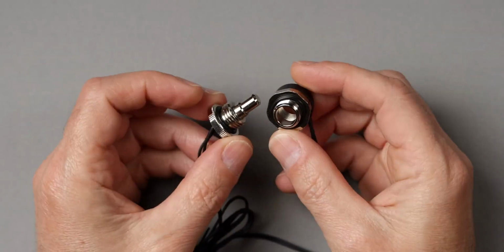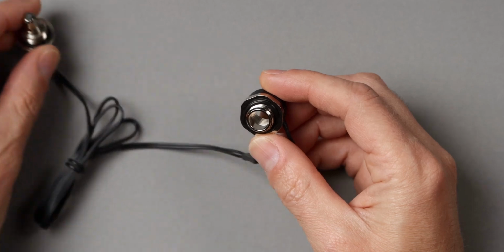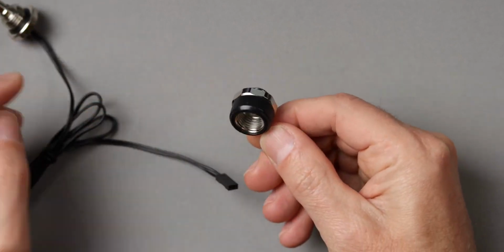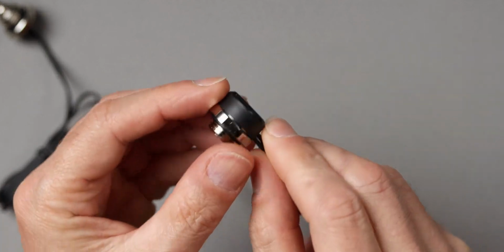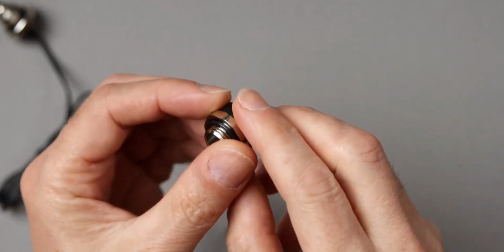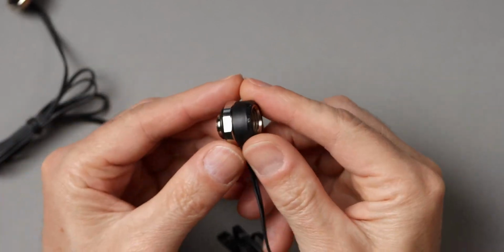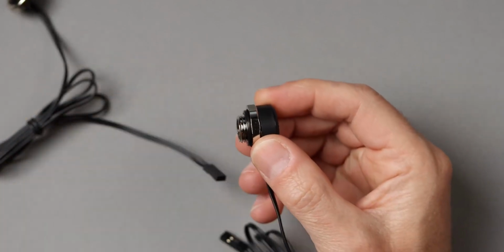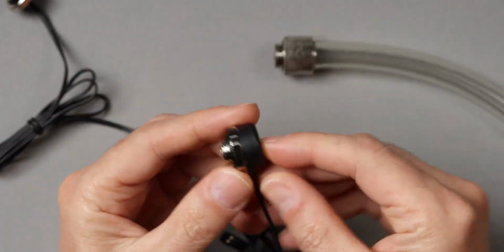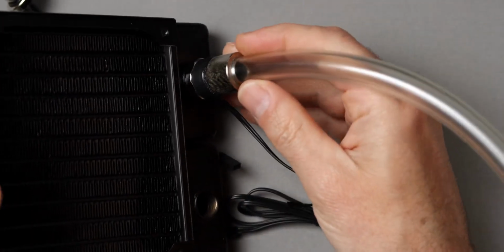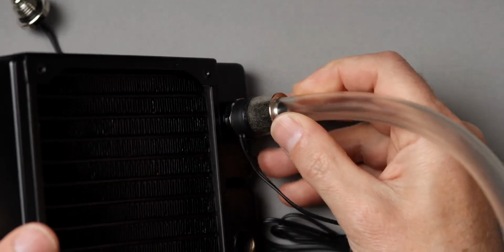For the sensor, you have some different options. I have two of the most common types here. Let's take a closer look at these. Here we have the two types of temperature sensors. This one is a ring type, where the water flows through the sensor. It can be placed virtually anywhere in the loop. This model has a male thread on one side and a female thread on the other side. You can, for instance, mount it in a fitting and attach both to a radiator. These are very easy to fit into the loop.